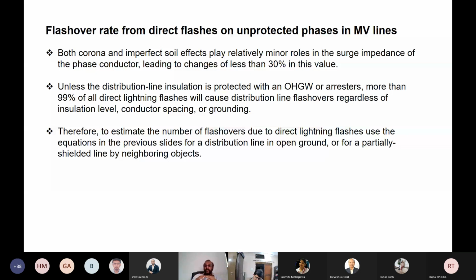We have done so many studies during the last 10-15 years on the corona and soil effects on medium voltage lines. Unless the distribution line insulation is protected with an overhead grounding wire or arrester, more than 99% of direct lightning flashes will cause distribution line flashovers, regardless of insulation level, conductor spacing or grounding. This is something that we have observed in Malaysia, Indonesia, and some Middle East countries as well.